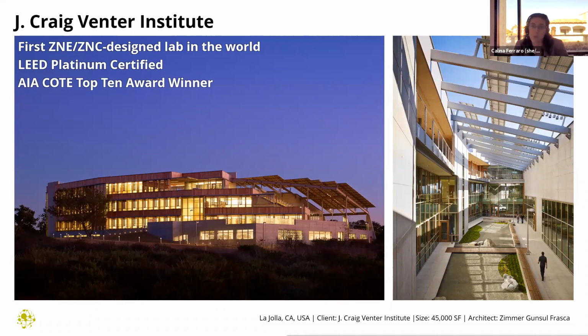We're able to shift those loads back and forth during the day and offset the majority of those loads throughout the year. Where we can't meet it just with that storage imbalance, we do have all-electric heating and cooling systems to meet the needs of the space. We also did a lot of energy recovery on the air side - where we're exhausting high air flows from the labs, we recover that energy through coils in that airstream as well. So again, it's about keeping that energy and reusing it, harvesting and storing it so we're able to shift loads to when we need them.